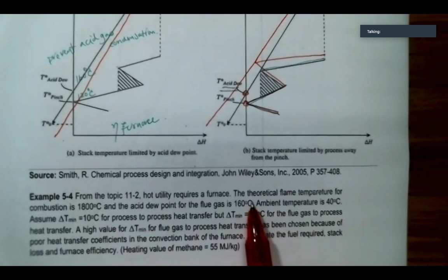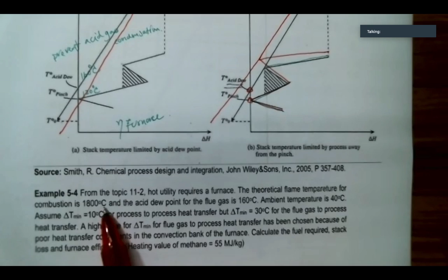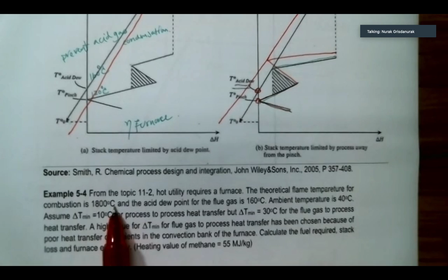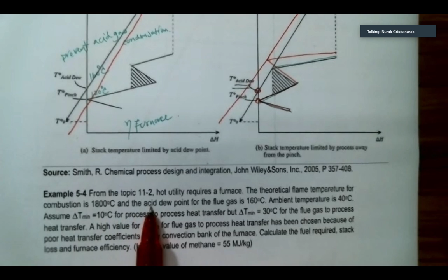Pilot flow, right? Now, if I already calculated that my system has combustion because the temperature I want may be higher than 250 degrees Celsius, I need to use natural gas or fuel oil to burn. After I calculate, I found that the flame temperature is equal to 1800 degrees Celsius. And there is some sulfur content in that fuel. So we have to consider the acid dew point, right? And the acid dew point is 160 degrees Celsius.